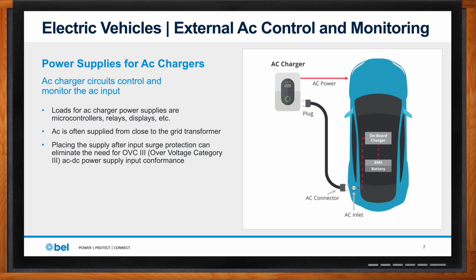In some European applications, there's also a concern about how the electrician connects it in, whether they've hooked it up line to neutral versus line to line. The problem is it's intended to be line to neutral, which is a lower voltage. Inadvertently, if they hook it up line to line, it's a higher voltage and can damage something. So the power supply either has to be tolerant of that, or protection circuitry has to be put in place.